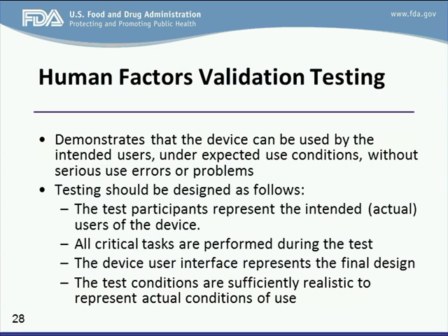So more specifically speaking, the test participant should represent the intended user of the subject device. All the critical tasks from your analysis should be included in the human factors validation testing. The device user interface that includes the physical interface as well as training, packaging, and labeling material should represent the final design and be used in your human factors validation testing. The test conditions of the validation testing should match the representative use environment of the subject device.